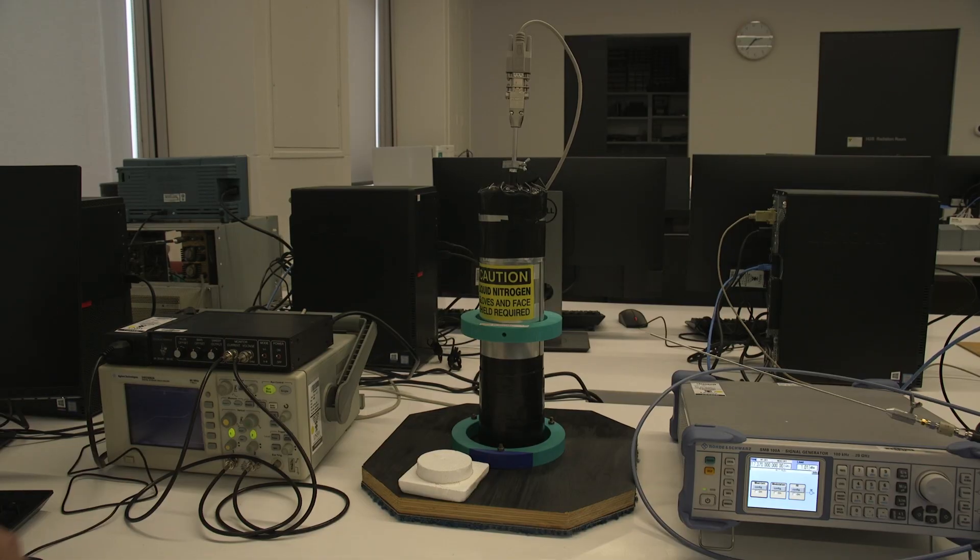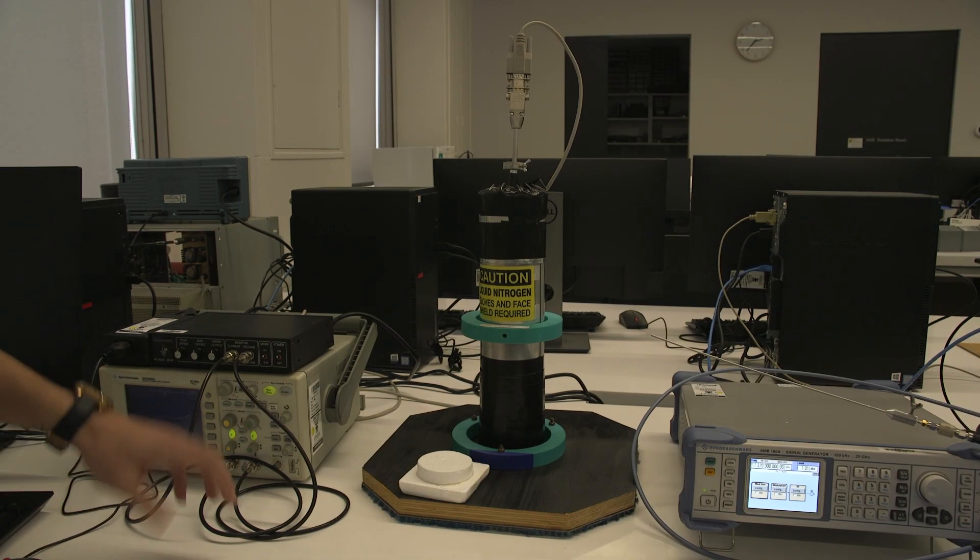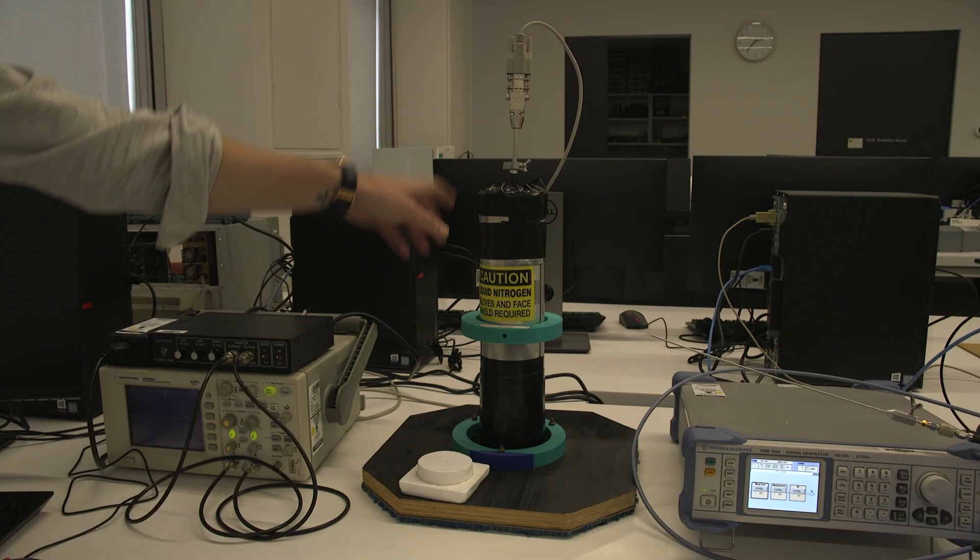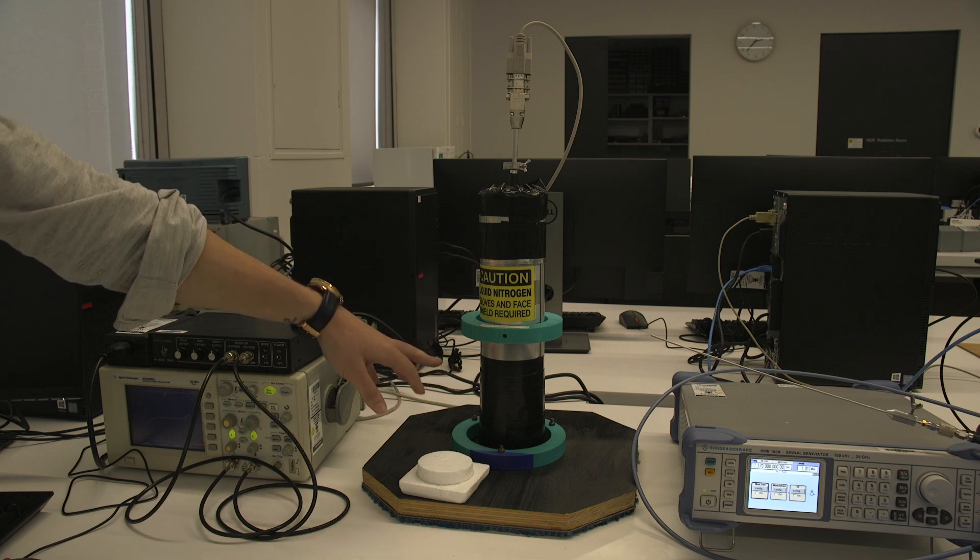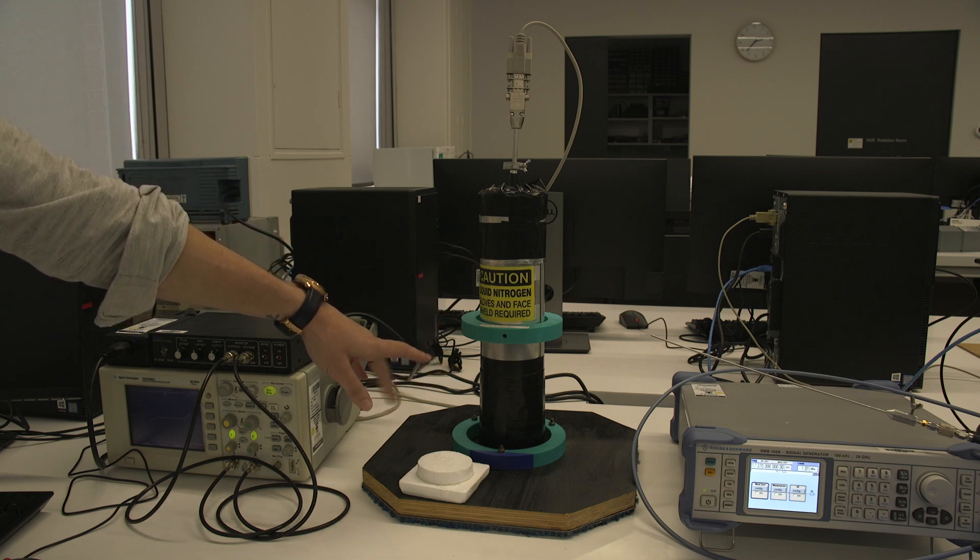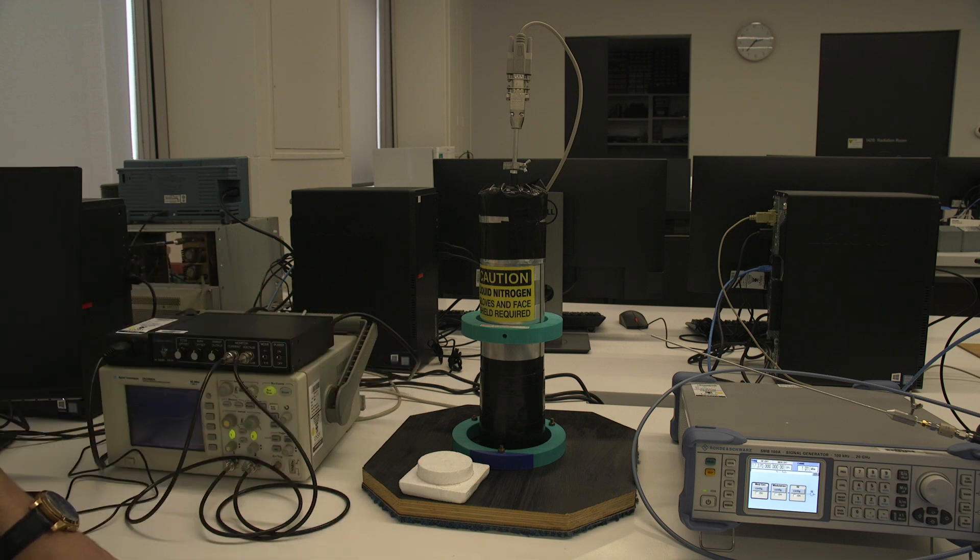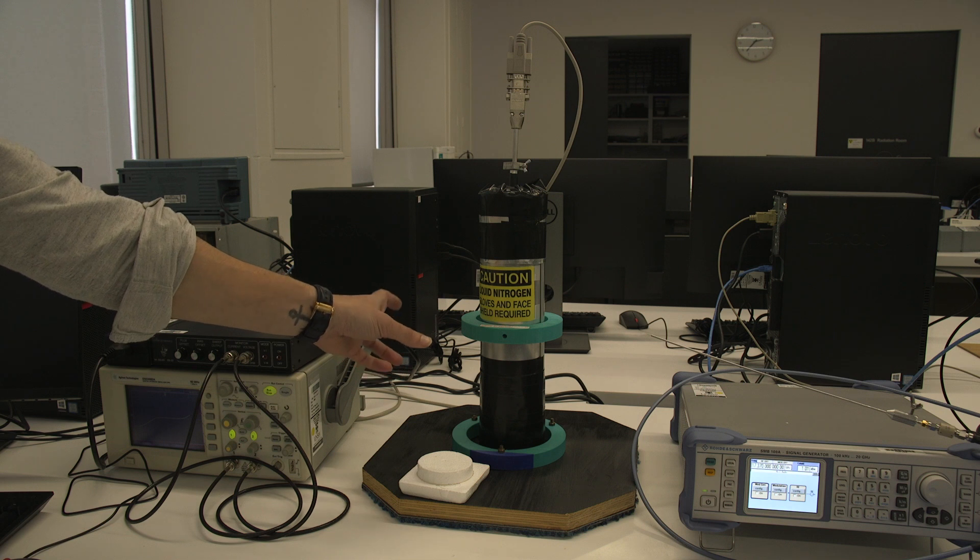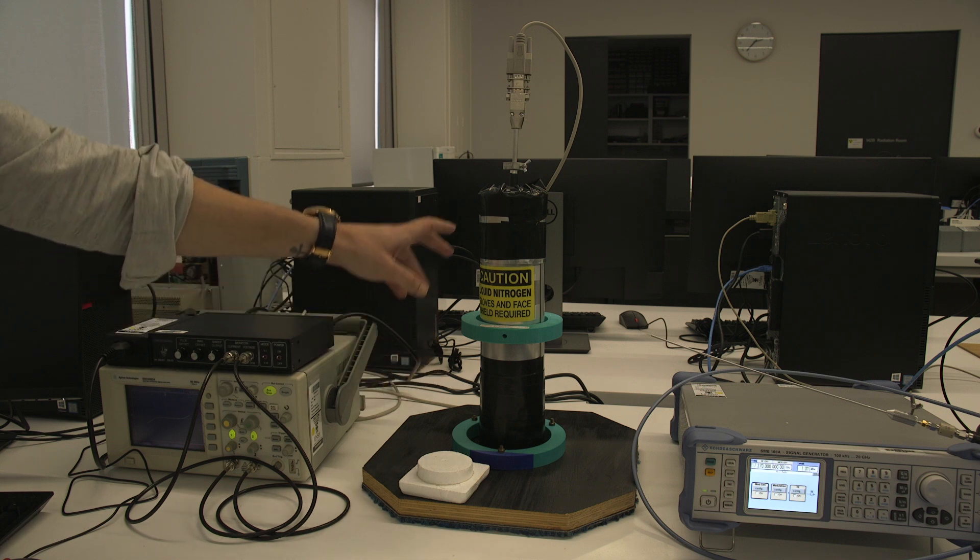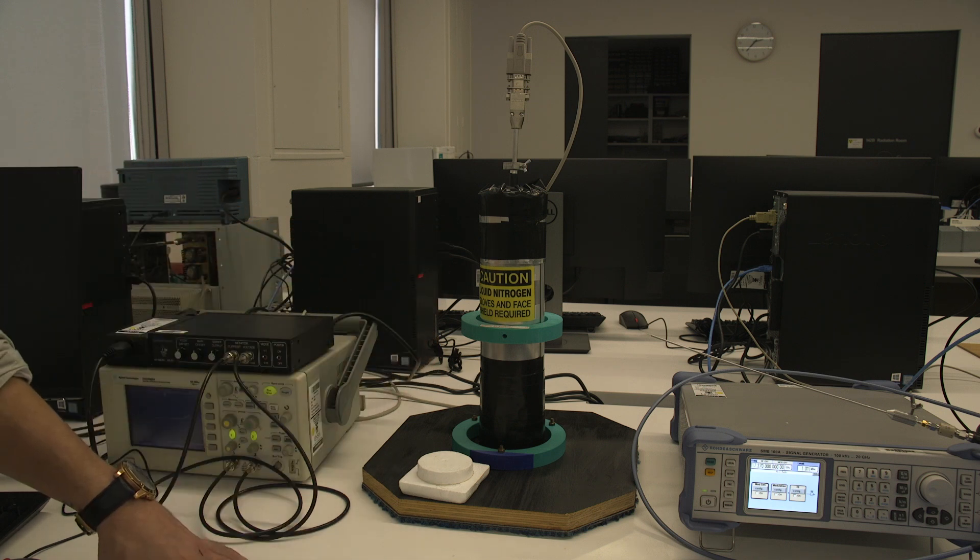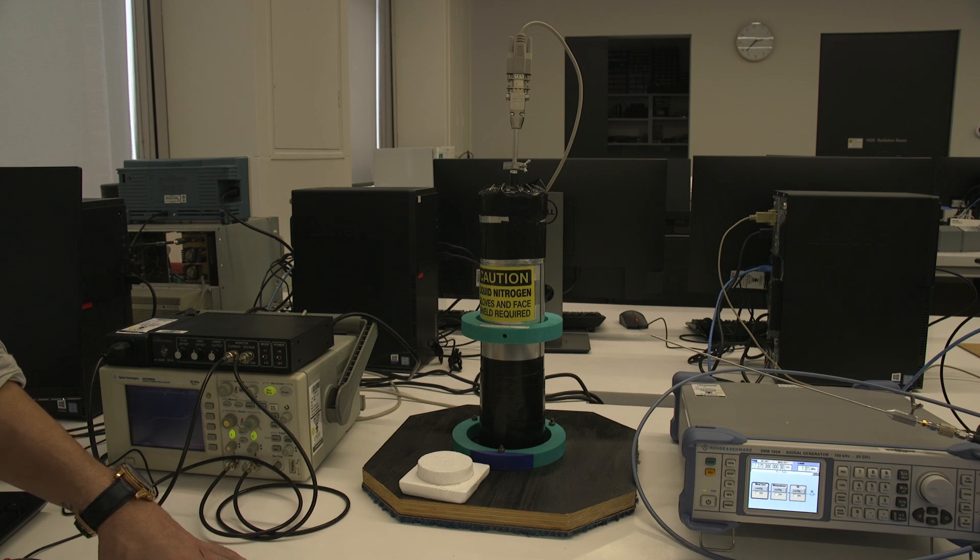Okay, so the SQUID device gets inserted into a liquid nitrogen bath to cool it down to a superconducting temperature. The dewar itself also provides shielding to the SQUID device because it's very sensitive to external magnetic fields, and we want to minimize that during the experiment.